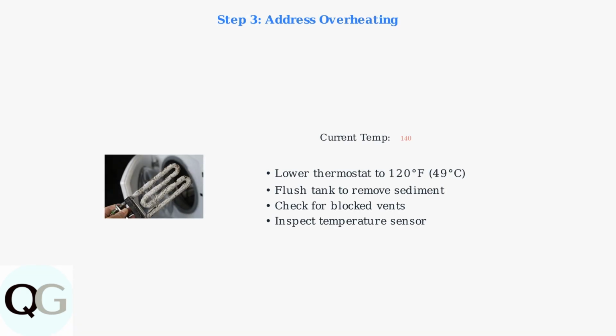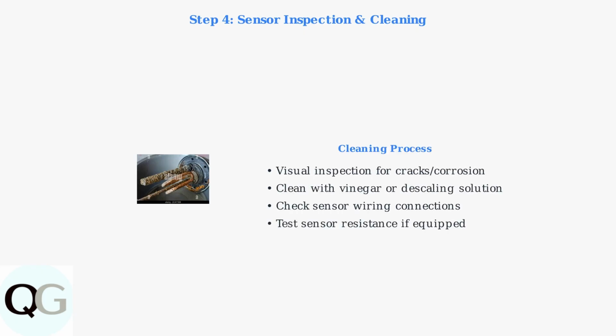Step 3. Address overheating issues. If your water heater shows 4 blinks indicating excessive temperature, lower the thermostat setting and flush the tank to remove sediment buildup. Step 4. For sensor-related issues indicated by 5 blinks, visually inspect the temperature sensor for damage such as cracks or corrosion, then clean it gently with a descaling solution.